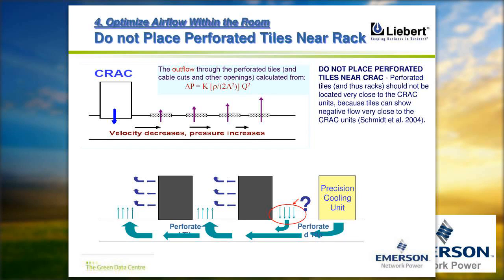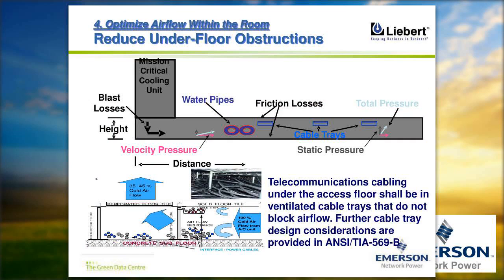Now, the recommended best practice is that you use power cable under the floor and copper and fiber cable above the rack. You can use a tray above the rack. That will simplify your airflow and remove a lot of restrictions which may come below the floor. So many times when you are using copper pipes or water pipes, it is important that they are planned properly. Many data centers in India, after 3 to 4 years, get piled up with a lot of cables, and most often it is seen that cables which require to be removed were never removed, only new cables get added.